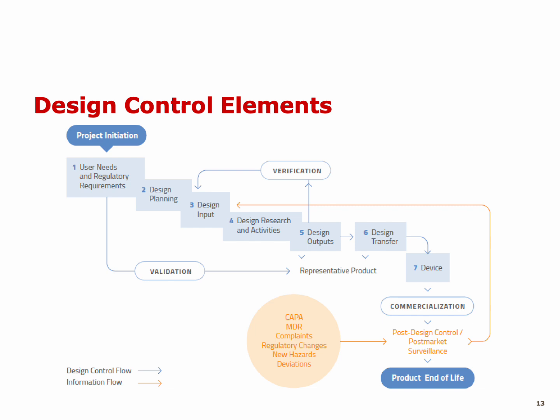Now we also have deviations. We may of course look into deviations where the process of making the device has been deviated and it will cause deficiency, but deviation can also be deviation from the best way to use the device. So here we talk about the instructions or the manual for using the medical device.